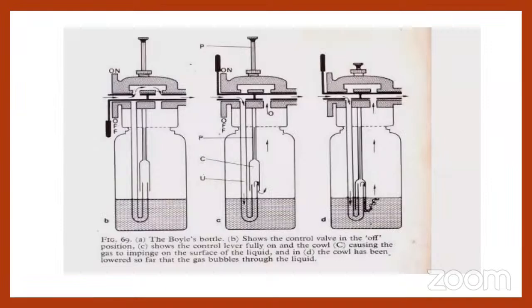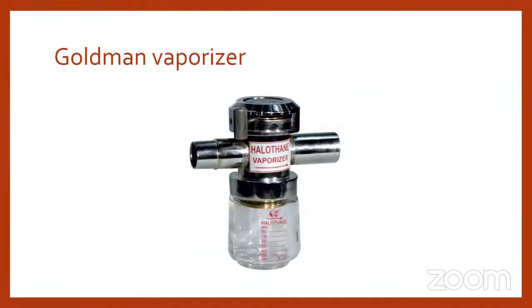The next kind of vaporizer is the Goldman vaporizer. It is a single vaporizer for use as draw over within a closed circuit system, designed by Goldman. It has no temperature compensation. Maximum concentration never exceeds 2% irrespective of total gas flow. It is a low efficiency vaporizer except during splashing. When we splash the liquid which is present in the bottle, the amount of vaporization will be more, so it will reach up to 5% concentration.